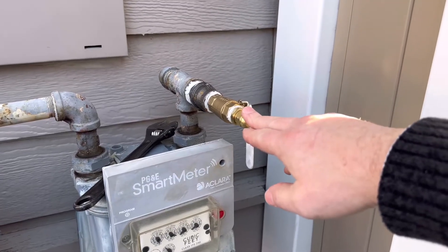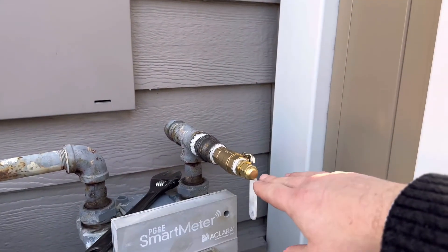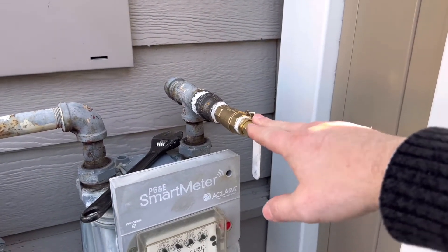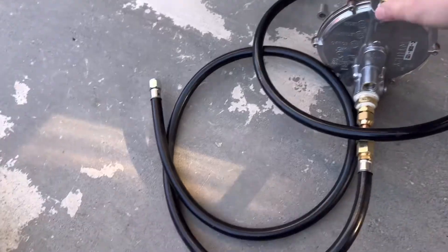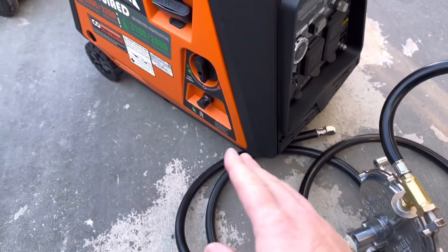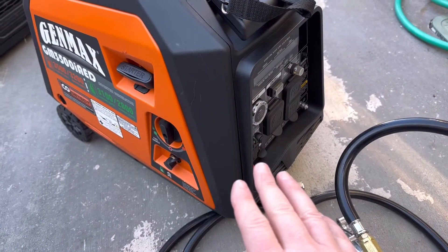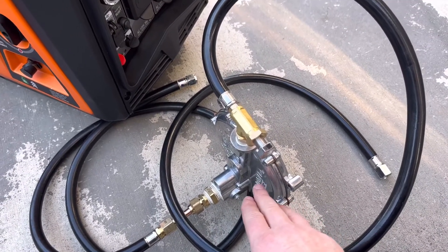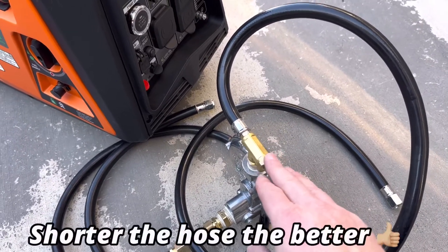Run a half-inch natural gas line at least 15 feet from your house — so probably a 20-foot line — then run it into the demand regulator. You want the demand regulator on a two to three foot hose going into the unit, keeping it as close to the generator as possible so the diaphragm inside works correctly under enough vacuum. If it's too far away, the generator will start to run poorly — keep it no more than about three feet from the unit.